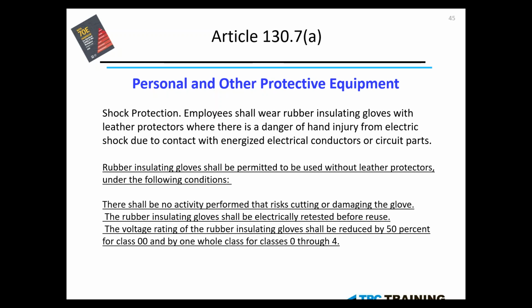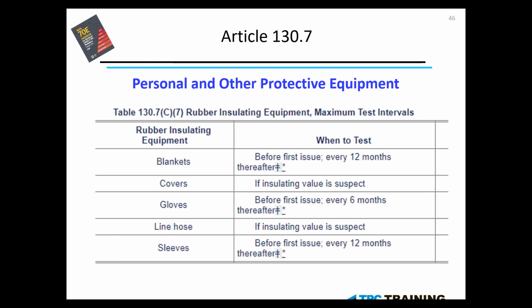There shall be no activity performed that would risk cutting the glove. Number two, the rubber insulating glove shall be electrically retested by a certifying agency after we use that glove, and we must reduce that voltage rating of the glove. So basically, we need to wear our leather protectors over our rubber goods. Table 130.7C7 also identifies the time in between these test requirements. We see there that gloves shall be tested before first issue and every 6 months thereafter. Again, we'll cover this more next month.